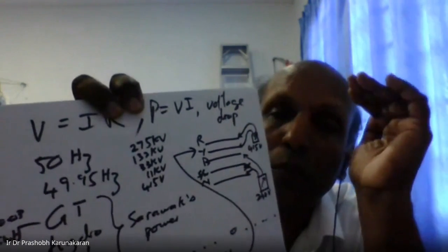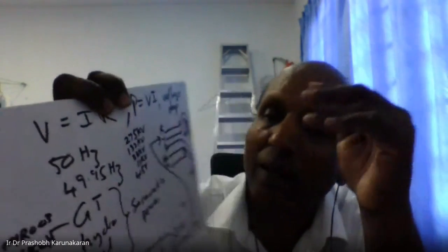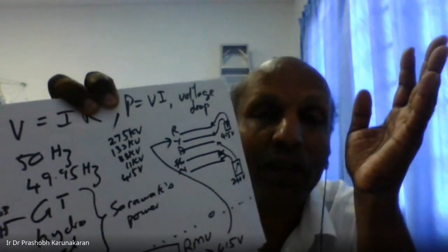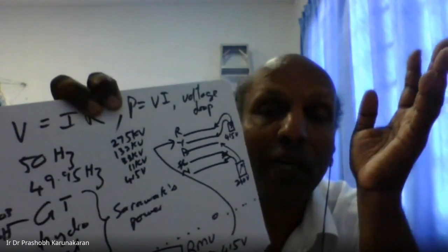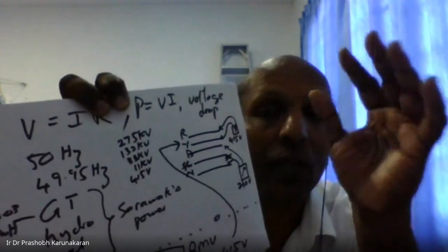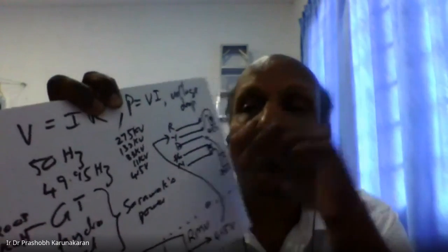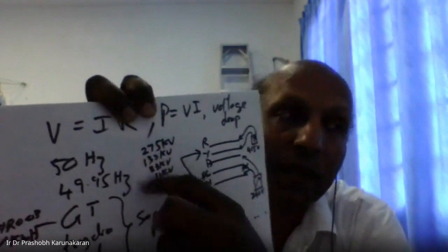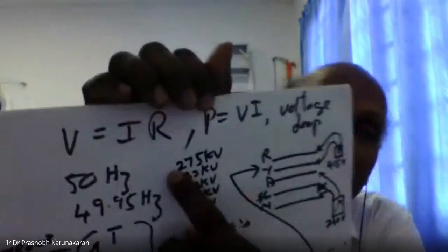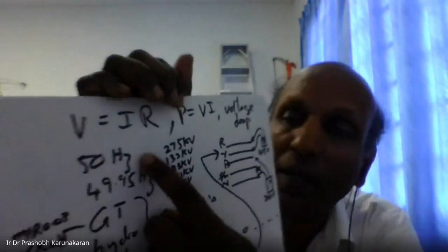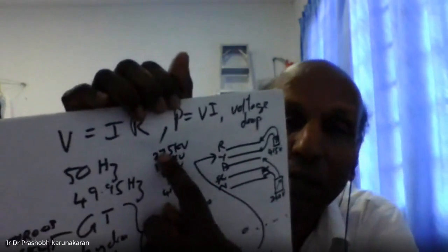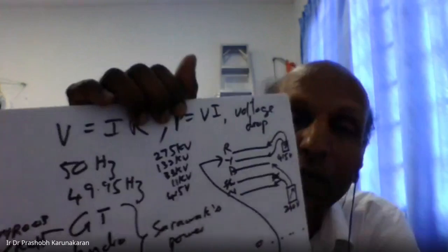That's supposed to run from Kuching all the way to Miri. But the 500 kV line is going to be energized at 275. That means the line is capable of 500 kV, but they're going to energize at 275 until a future time, when in all the substations they have to change the transformers to 500 kV. Right now it's 275, so the main artery of Sarawak is 275, between Kuching and Miri. They haven't gone to Lawas yet, they are building to Lawas right now. From this main artery, they take out all the smaller voltages.